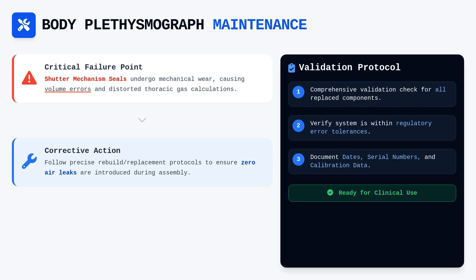Once any component, be it a seal, a sensor, or a circuit board, is updated or replaced, you must perform a comprehensive validation check. This is not optional. It is a regulatory requirement that proves the system is still operating within the specified error tolerances. Your documentation should clearly state the date of the maintenance, the serial numbers of new parts installed, and the post-maintenance calibration data confirming that the system is ready for clinical use.